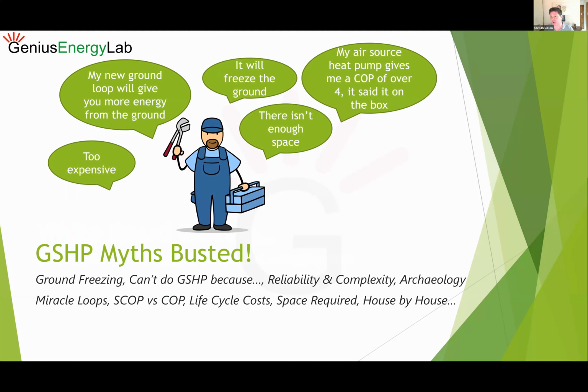We've got propylene glycol in there. But if you are seeing adverse effects on structures at the surface due to what the ground loop's doing, then that loop is just not well designed - it's an unsustainable loop. I've got some horror show pictures of somebody who put loops in the sand under their patio - first winter, it just buckled and heaved. So if you're seeing any negative effects due to that ground loop, it's inadequately designed.